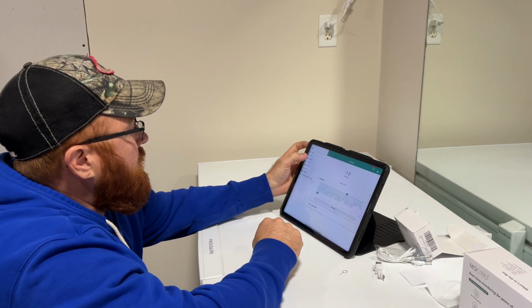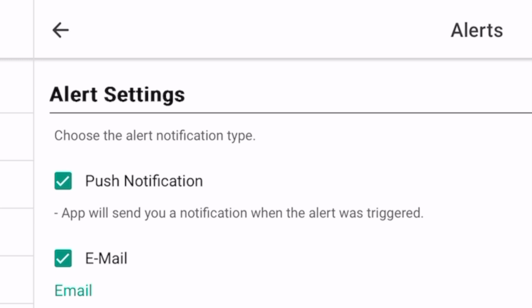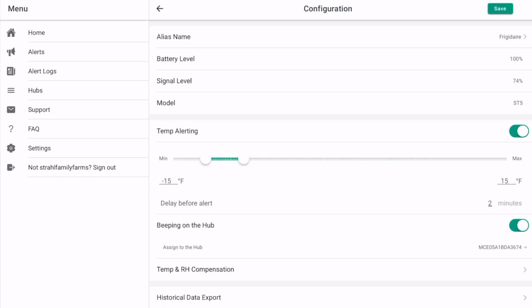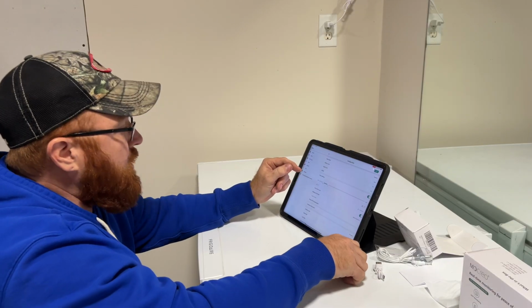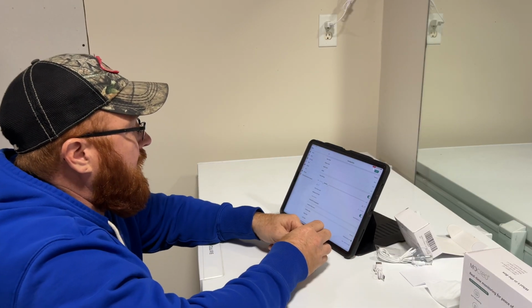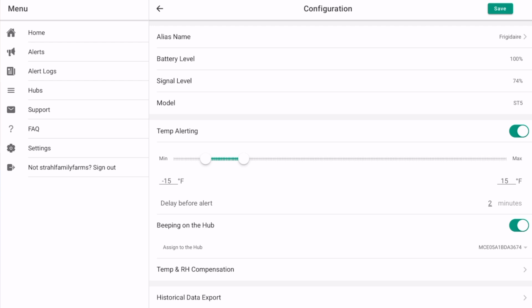If you go into the alerts section, this is where you can set up push notifications to have it email and alert you. Going back into the freezer sensor and clicking the wheel shows all the parameters you can set — you can see temp alerting, which you can turn on, and set a minimum, maximum, and how long you want it to delay before alerting you. For me, I've set it between -15 and +15 degrees Fahrenheit for now, with a 2-minute delay to allow for a fluke where the sensor might stop reporting for a second, so I'm not getting false readings and freaking out while I'm away.